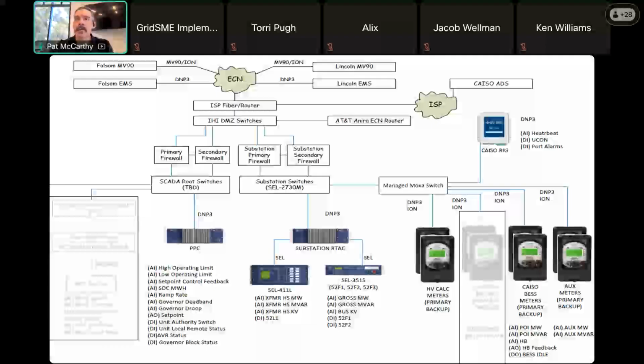The other folks you'll want on hand for your point-to-point test are your power plant controller folks. If you have multiple resources controlled by different people, depending on which resource is having its point-to-point test, those folks need to be on a call and able to remotely access that power plant controller and simulate values as far back into their system as they can. What you want to prove there is the logic of the power plant controller itself, as it's calculating these points, as well as all the protocol implementations between that device and the rig.